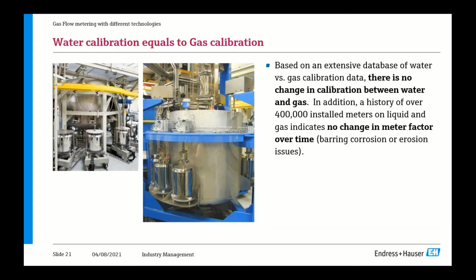After some experience, it is likely that our customer, of course, will repeat step 3, which is once again removing the device from the site. It will actually be extended to maybe 2 or 3 years after they see that there is no change in the meter factor over time. So this is a very, very important and big advantage of Coriolis meters, of course.